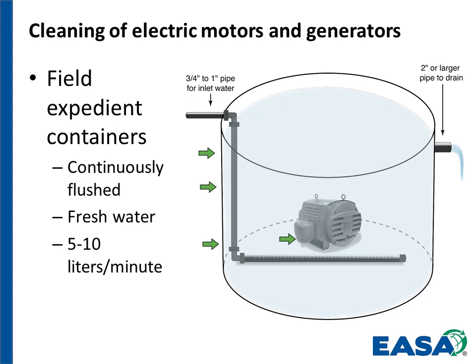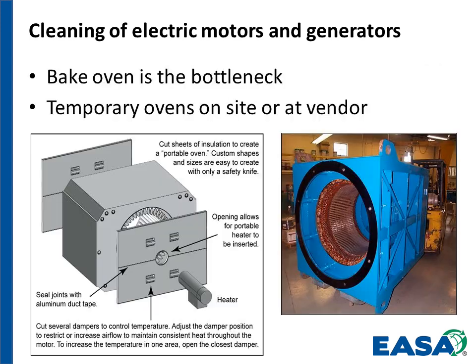So this tank full of fresh water is just here for the purpose of avoiding the salt water actually being allowed to dry. Now, next slide, cleaning of electric motors and generators. In a typical service center, the bottleneck is the bake ovens. We have possibly 14,000 electric motors in one plant that I'm thinking of in Deer Park, Texas. To run all those electric motors, some of them quite large, like the one you see here on the right side of the slide, through pressure wash and then process them through a bake oven to dehydrate them, a stator this large might take 10 or 12 hours to fully dry and remove all the moisture. So the bottleneck is the bake oven that's being used to do that.